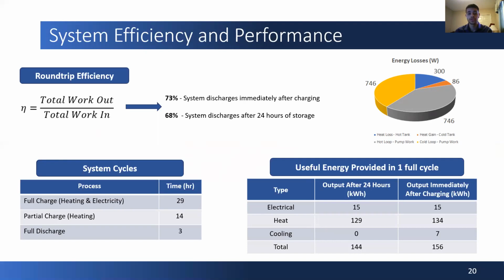However, if the system was to store energy for a total of 24 hours, we would only get an efficiency of 68%. The majority of losses here are due to the pumping work required to circulate the working fluids that are in the system, followed by the heat loss through the hot tank during storage.